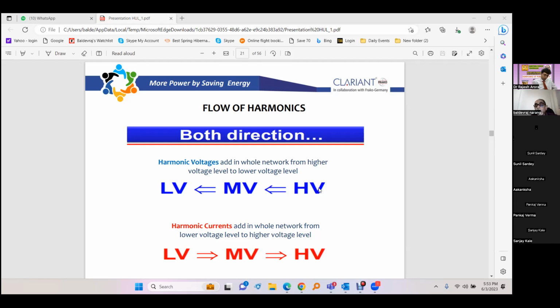If they don't maintain the voltage harmonics, because they will go back to every consumer, whether they have linear load or non-linear load. So they have to pay a penalty to everybody for excessive voltage harmonics, which are out of the limit of the IEEE 519 norms. So the number of people who will be getting the penalty from grids will be more than the people who are exporting current harmonics. So maybe these people are very slow in getting these norms implemented.